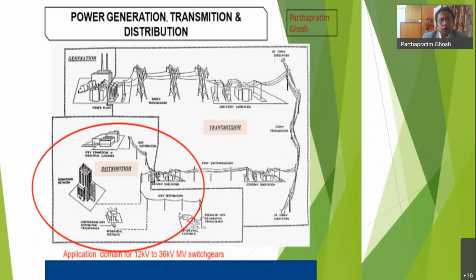The encircled portion, the below left corner, is the distribution segment, and medium voltage switchgear rated typically 12 kV and 33 kV is placed and is functional in this particular domain, not in the transmission segment. There are different kinds of EHV circuit breakers for that.